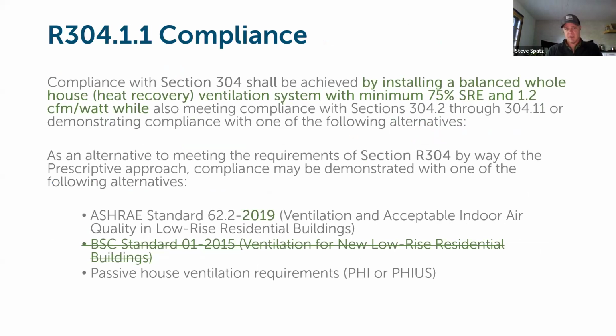So there is a minimum performance requirement called out in the code for equipment, which has a minimum sensible recovery efficiency of 70%. This has changed, so I apologize for that number being off here. So the minimum performance requirement is 70%. That's sensible recovery efficiency. That's essentially how effective the heat recovery core is at extracting BTUs and heat energy from the exhaust stream and putting those into the incoming fresh air stream of the system. And then a minimum fan efficacy, a fan efficiency essentially, of 1.2 CFM delivered through the system per watt of electricity consumed to move the air.